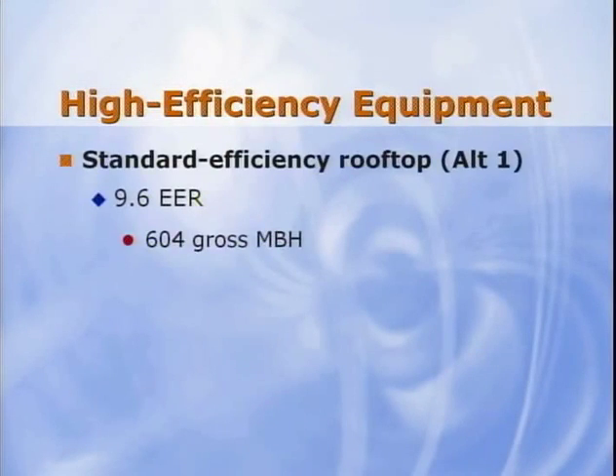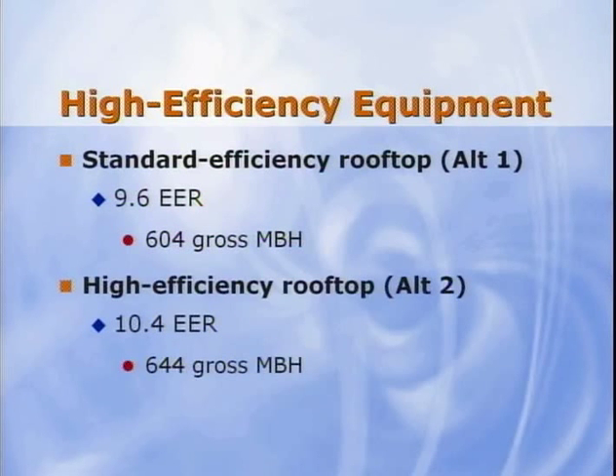To demonstrate the efficiency gain between standard and high efficiency rooftop systems, we can compare two 50-ton units, one with a standard refrigeration system and standard efficiency supply fan motor, and one with additional evaporator and condenser coil capacity and a high efficiency supply fan motor. Because application requirements vary widely, we've chosen to use ARI rating conditions for both units. At these conditions, the standard unit yields an energy efficiency ratio of 9.6 and 604 MBH gross capacity, while at the same design conditions, a unit with additional evaporator and condenser coil rows and high efficiency supply fan motor yields an energy efficiency ratio of 10.4 and 644 MBH gross capacity.